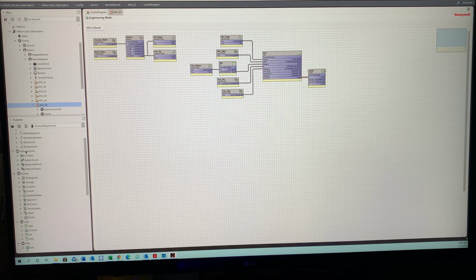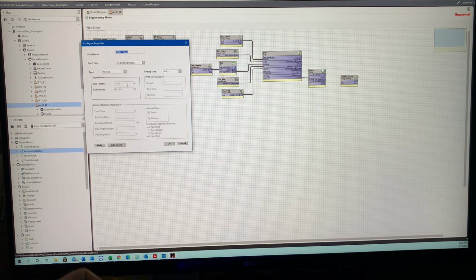So for this, we're going to do a modulating output. We're going to call this chill water valve command, and that's going to be our AO. We'll go to configure properties. I'm not saying all the different brands have different ranges. We do a lot of Belimo and a few other products, but mostly it's Belimo product that we see out here in Houston. So it's a 2 to 10. Obviously, they come 0 to 10, but the ones that are always on the shelf and available for us are the 2 to 10. The cool part is you can modify this to whatever you want.